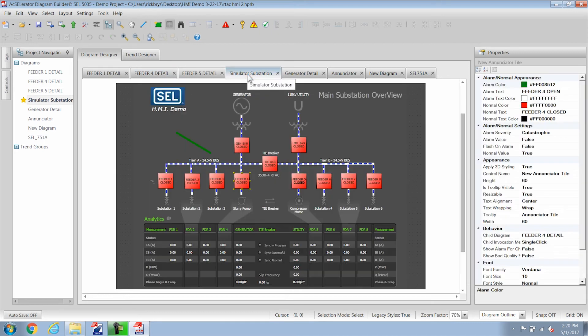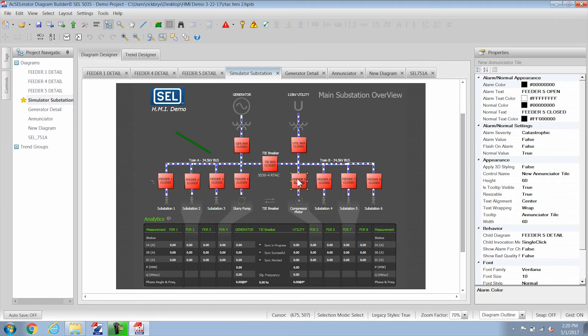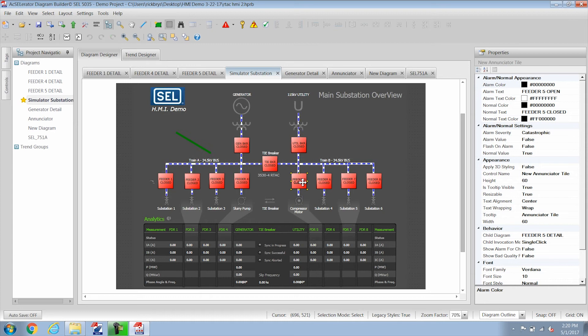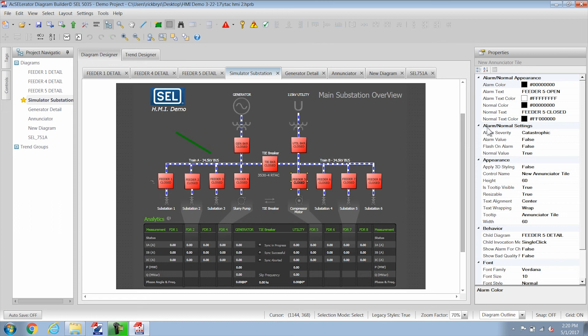And the last thing I want to cover about annunciator tiles is you can make them invisible. So if I wanted to have a control object that is a particular type that is not in diagram builder right now I can build that in paint or whatever kind of drawing package that you want and then lay an annunciator tile over it. And here I have changed the annunciator alarm color and normal color to all zeros and that indicates that it's going to be a transparent property.